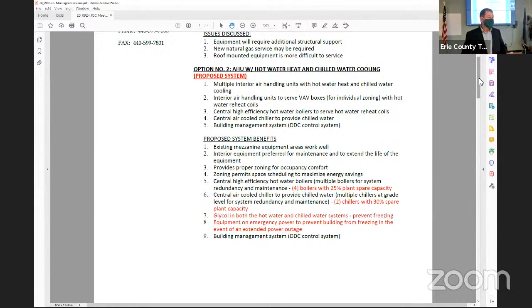With both of those systems, we're proposing glycol in the systems to prevent freezing. You certainly don't want to have hot water or chilled water coils in the air handling units and have them freeze because something fails open, one of your outside air dampers, whatnot, and cause any freezing issues.